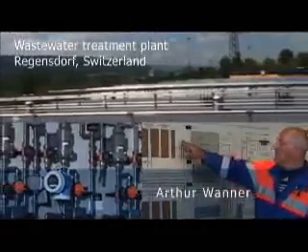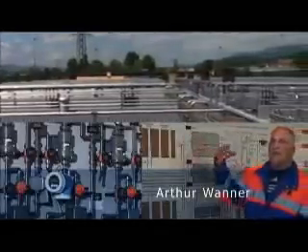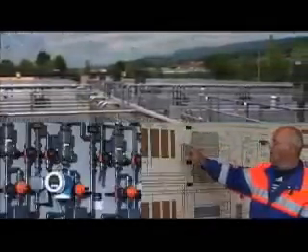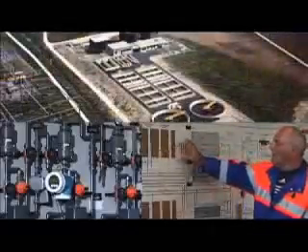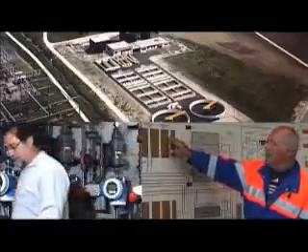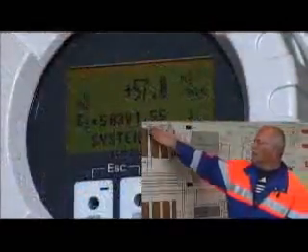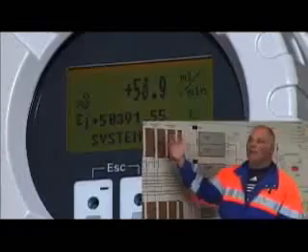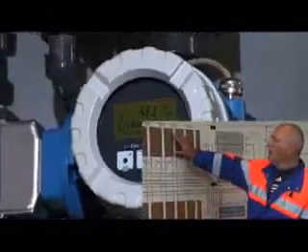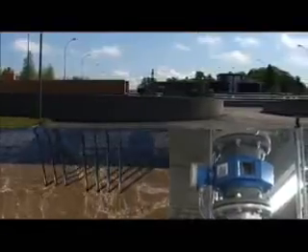Long-term stability is a keynote in the wastewater industry. This environment here is much harsher than in the drinking water industry. Wastewater is chemically aggressive, so too are the substances used to treat it. Piping and flow meters have to be designed to withstand, and the materials have to be just right. This is especially true in the iron chloride injection station. Iron chloride is used to leach phosphates out of the sewage slurry. The substance is aggressive, however, so PVC pipes are used for the injection stations in combination with Endress & Hauser sensors with PFA linings.